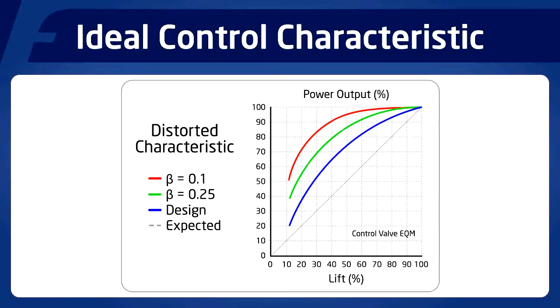However, the lower the authority of the valve, the more of a quick opening style valve it becomes, and less control is exerted by the control valve, very often leading to hunting and unstable temperature control. So clearly, choosing a high authority for a control valve is very important.